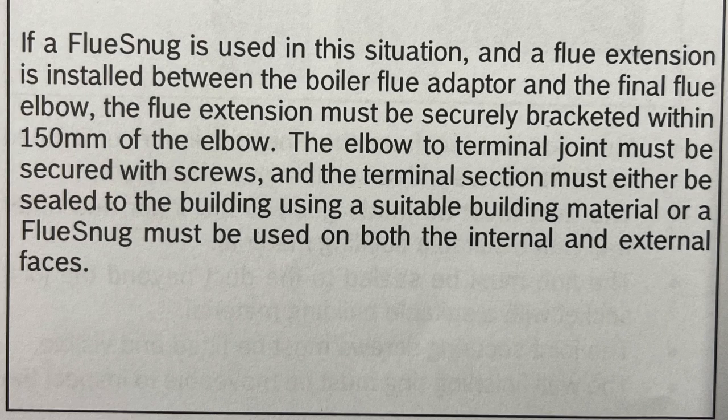Worcester, in their technical bulletin, tells you exactly how to install the Flue Snug. They basically say: if the Flue Snug is used and a flue extension is installed between the boiler flue adapter and the final flue elbow, the flue extension must be securely bracketed within 150mm of the elbow, and the elbow to the terminal joint must be secured with screws. The terminal section must either be sealed to the building using a suitable building material, or a Flue Snug must be used on both the internal and external faces. So that is another product you can use to seal your flue without the need of sand and cement, foam, or silicone.